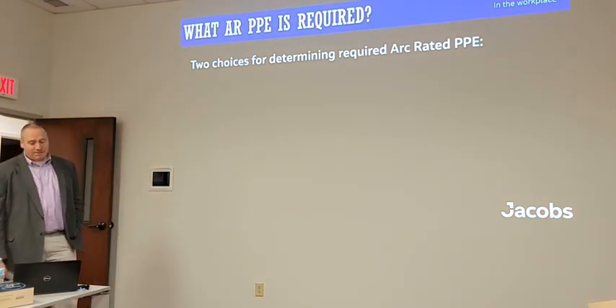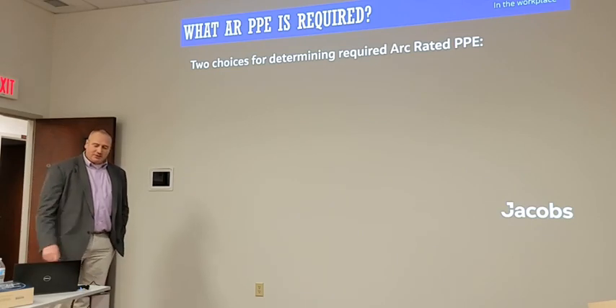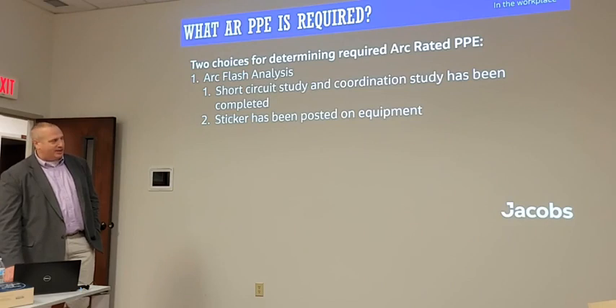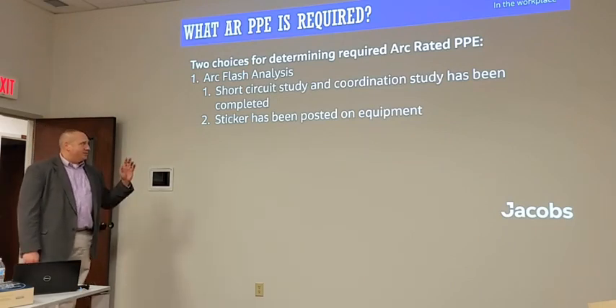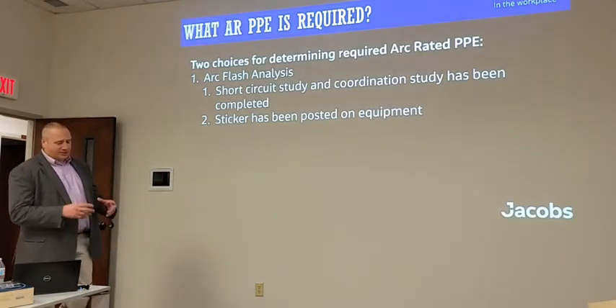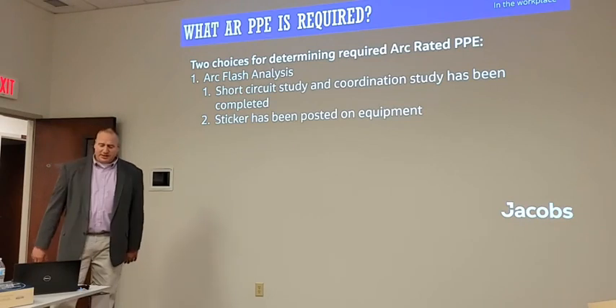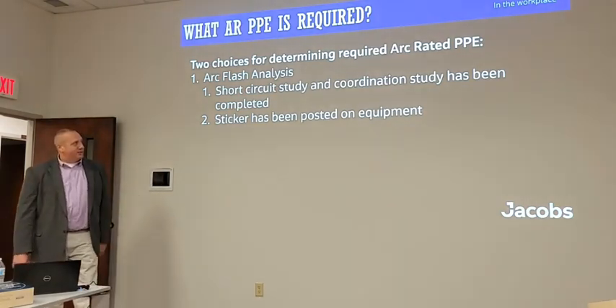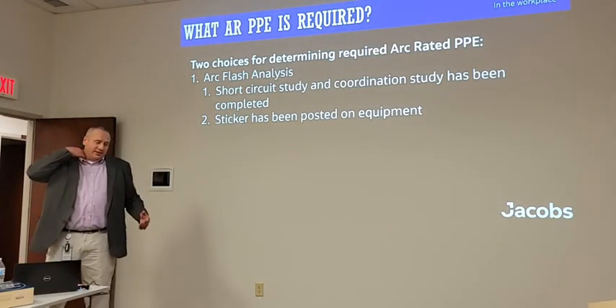So there's two choices for determining what the required PPE is that you need. The first is arc flash analysis. And that's where you do the short circuit study, coordination studies completed. You've got the incident energy analysis, and the sticker's been posted on the equipment. That's the easiest.